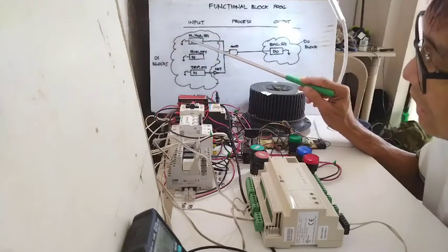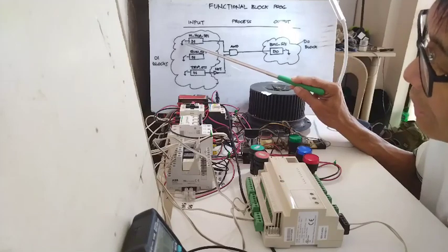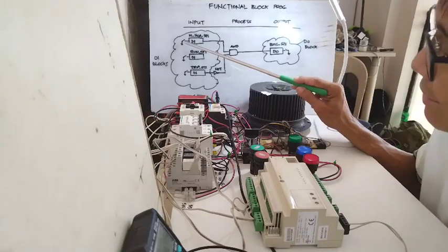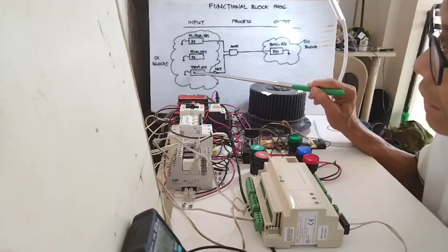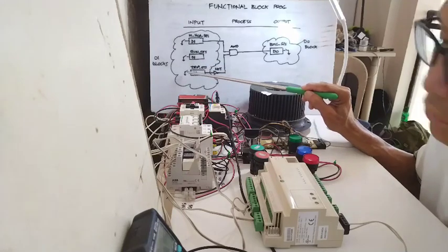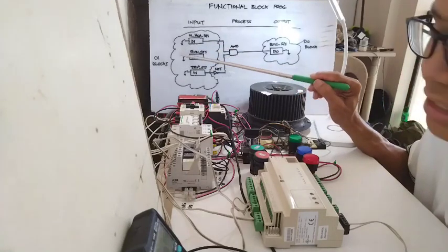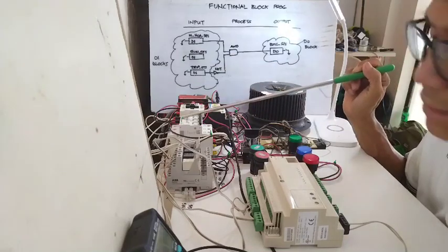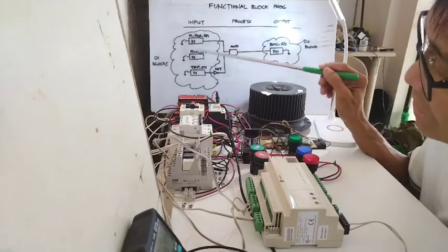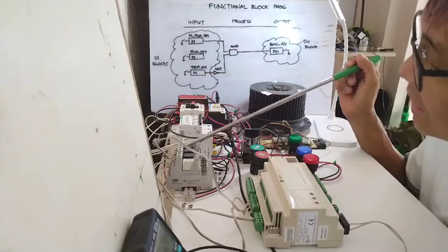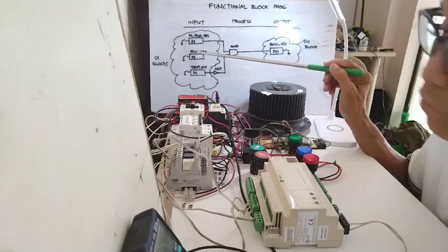As you can see, there is information here showing that this one is coming from a normally open contact — just like this running status, also coming from a normally open contact. Then trip status will also come from a normally open contact. These contacts are the ones we provide in our control panel. We call these BMS points — these three relays here.